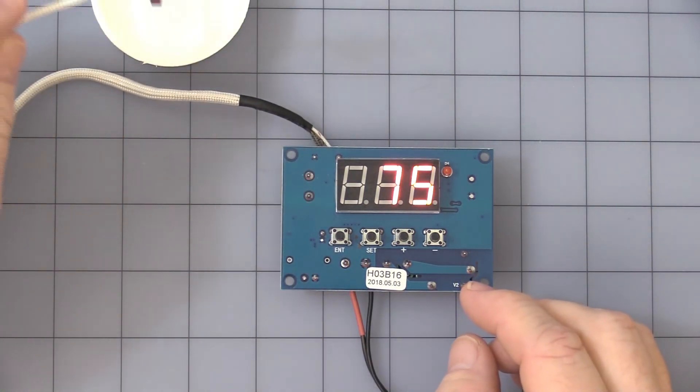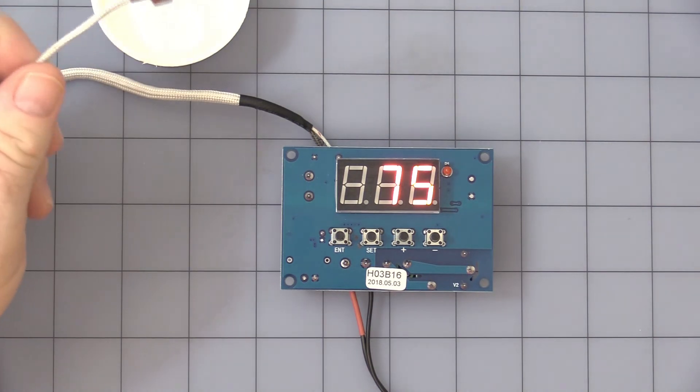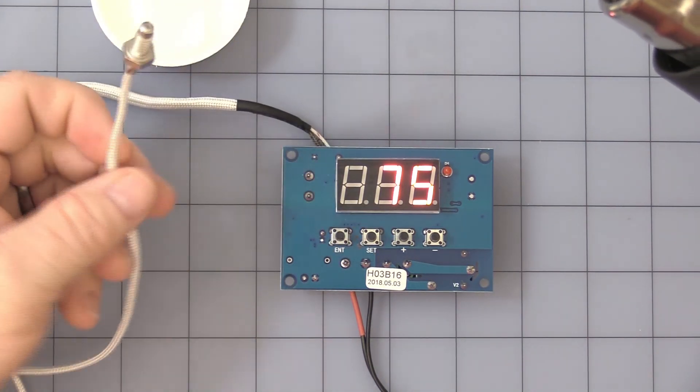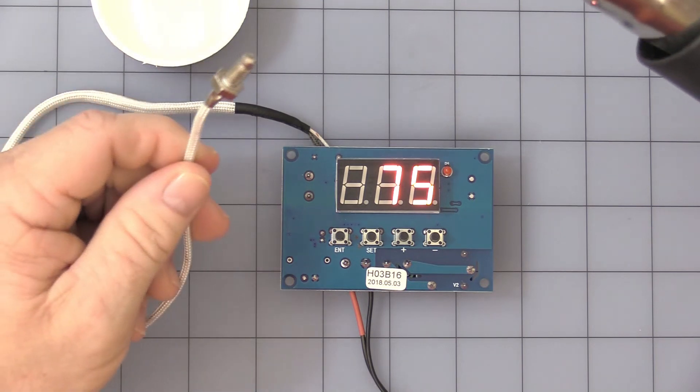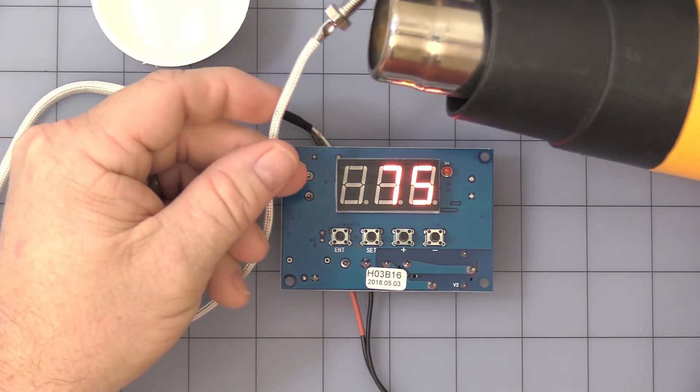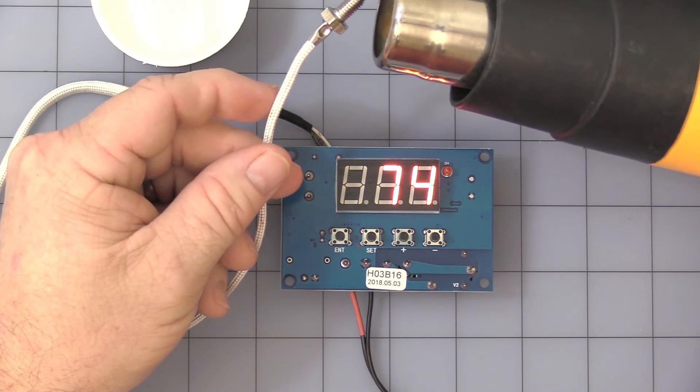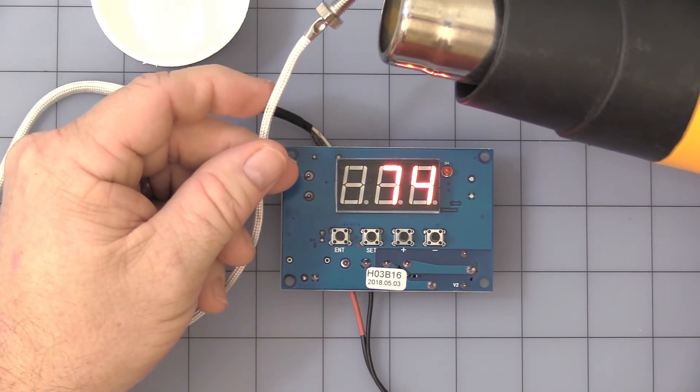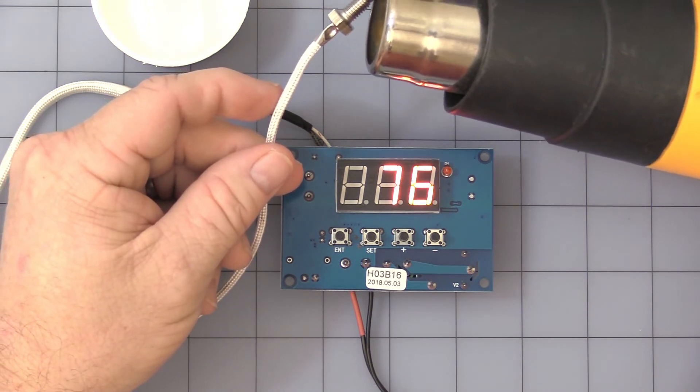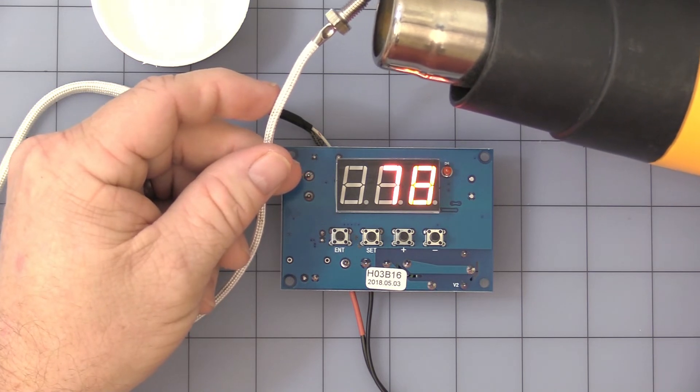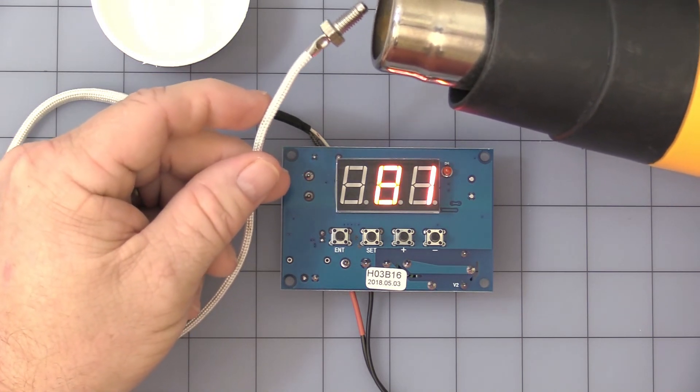Okay, that means when the probe gets up to 100 degrees Celsius, it will turn on. Actually 105 because there's a 5 degrees hysteresis. So as soon as it gets to 105, it will turn off.